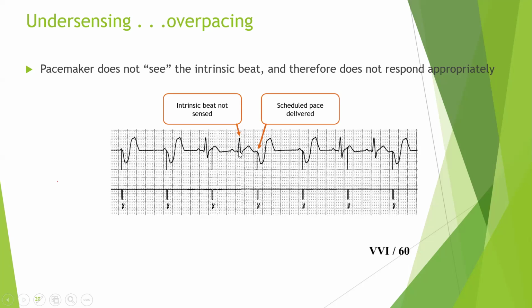Fortunately, here it paced after the completion of the T wave. Completion of the T wave means that the relative and the absolute refractory period is finished. And here, if pacing happens, it will depolarize the ventricle and it will not cause arrhythmia. So you can see clearly here now, it happened after the T wave completed and as a result, it is capable of capturing and depolarizing the myocardium. So V pace. Then again, this is appropriate pacing because there is no intrinsic rhythm happening before it.